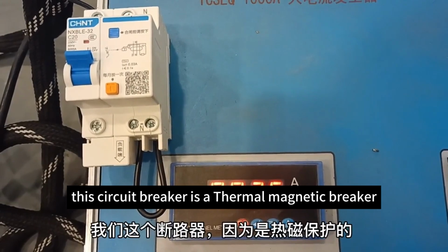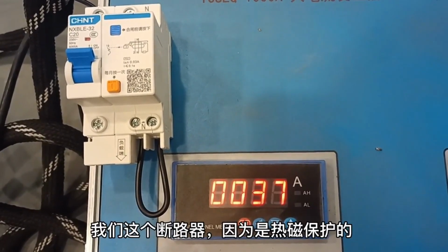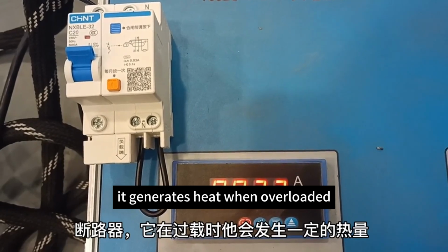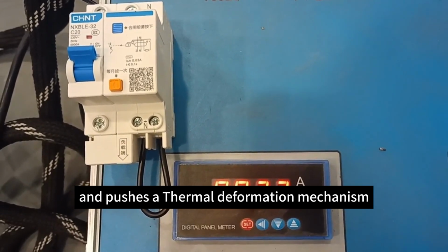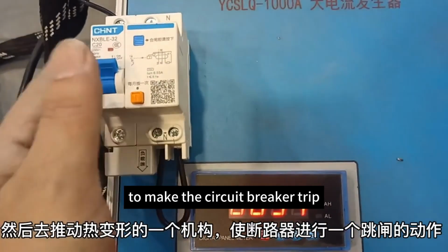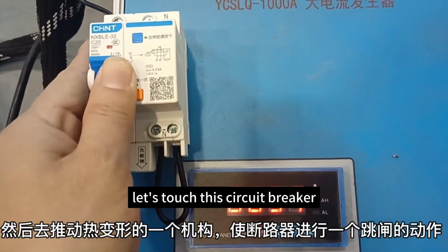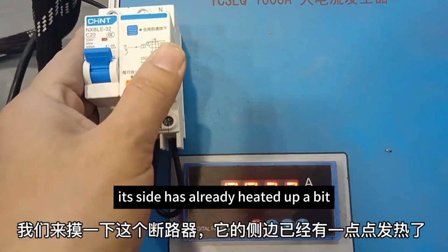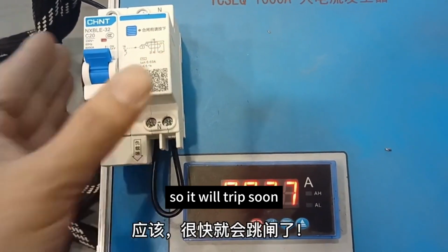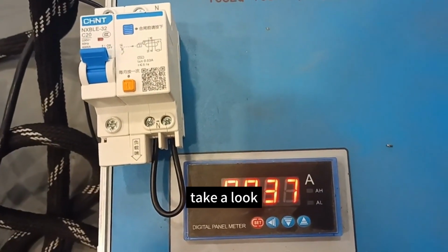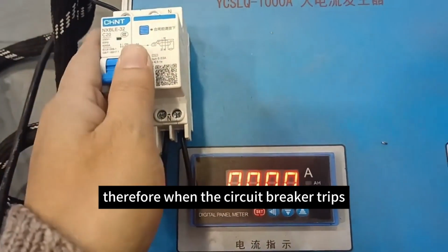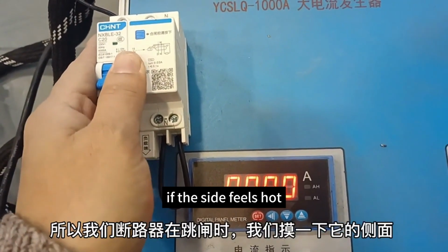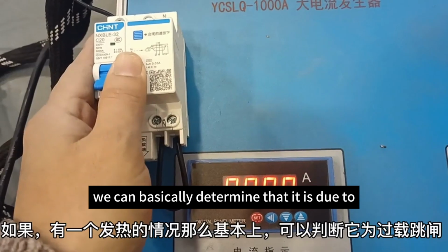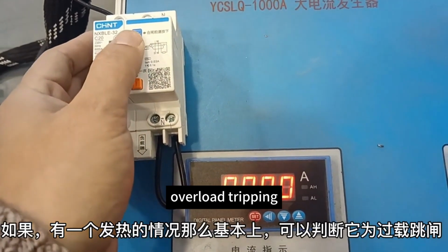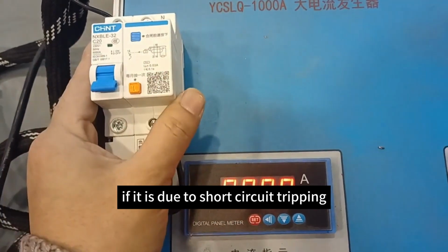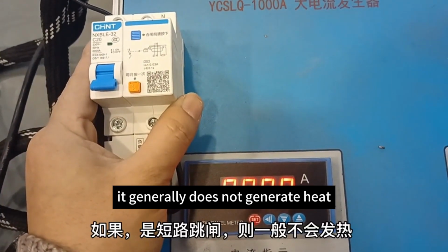This circuit breaker is a thermal magnetic breaker. It generates heat when overloaded and pushes a thermal deformation mechanism to make the circuit breaker trip. Let's touch this circuit breaker. Its side has already heated up a bit, so it will trip soon. Take a look. It has tripped now. Therefore, when the circuit breaker trips, if the side feels hot, we can basically determine that it is due to overload tripping. If it is due to short circuit tripping, it generally does not generate heat.